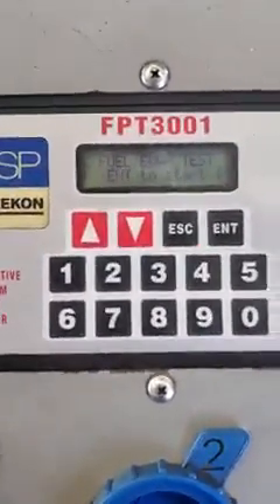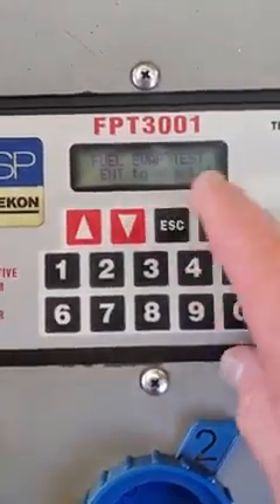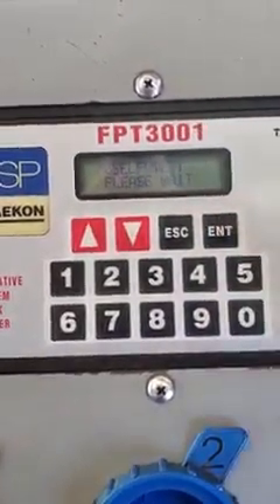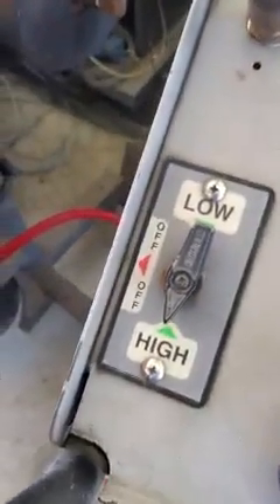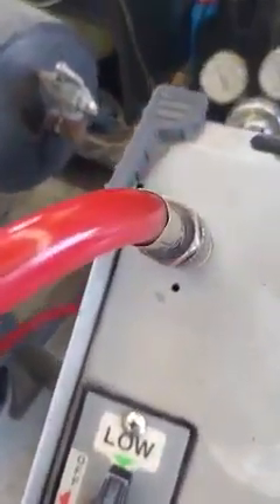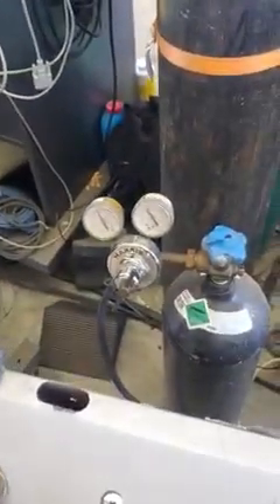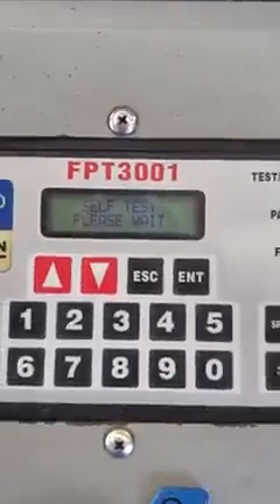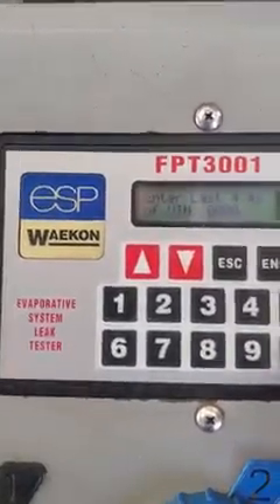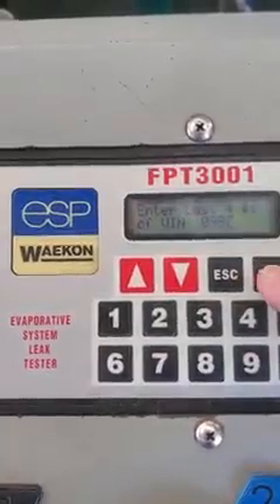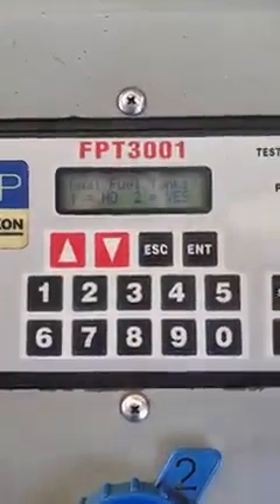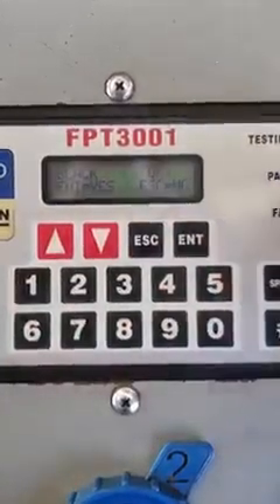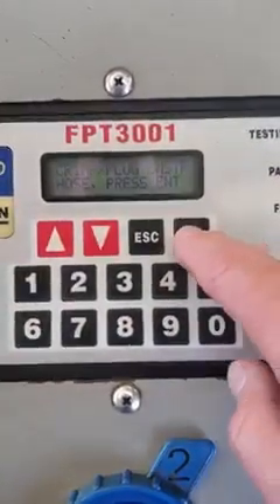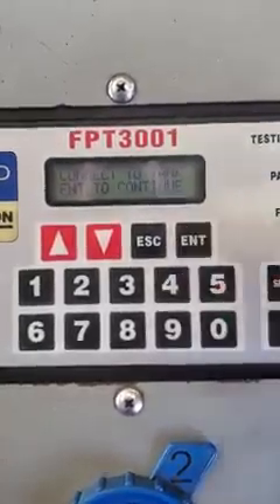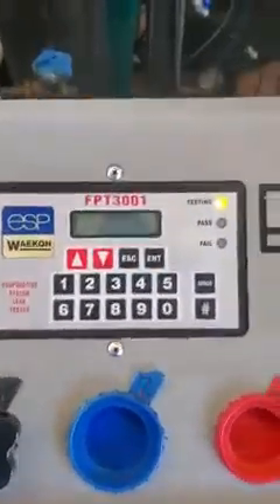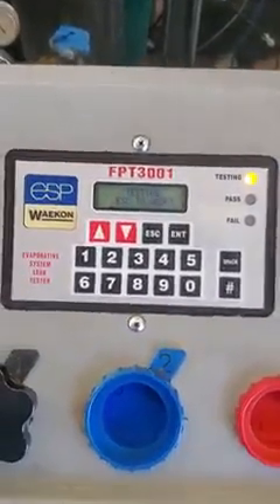If you want to test your machine to see if it'll do an official test, you're on your home page, push enter. Your high-low valve is on high, your red hose is connected, and your gas is turned on. So now you can enter any 4 numbers, push enter, 1 and 1, and enter again, and enter, and one more enter. Now the machine is doing an official test using the calibration tank.